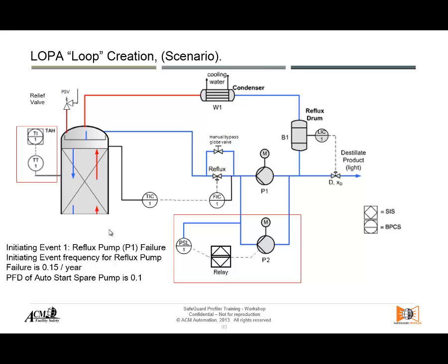That's the event PSV failure, or the failure on demand. Now we also have another event that has to happen for the progression of that towards the unwanted event. Now the temperature safeguard alarm would have to fail. So what are the chances now? What are the probabilities that the PSV fails and that the temperature alarm fails? So how do we account for that? We multiply the two probabilities of failure of both of them, and of course the number is smaller and smaller all the time. And that's the way that we represent how we reduce the likelihood of that initiating event developing all the way and becoming the unwanted event.